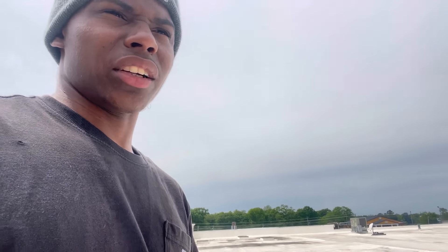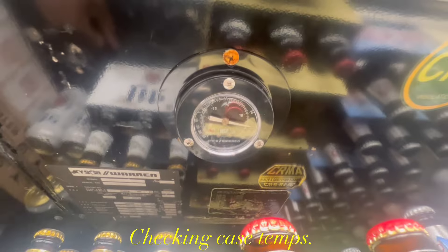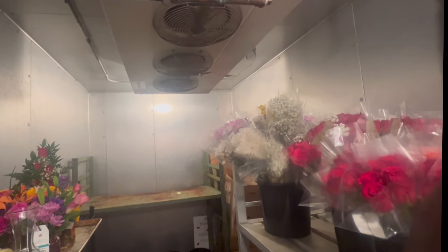I've got to find the condenser — the condenser looks like it's right here. I'm going to verify to make sure I don't have any leaks. Very clean store. Case temps are coming down. The compressors are now running. It's probably going to take a while — this case has been off for a while. Feeling way colder in here.